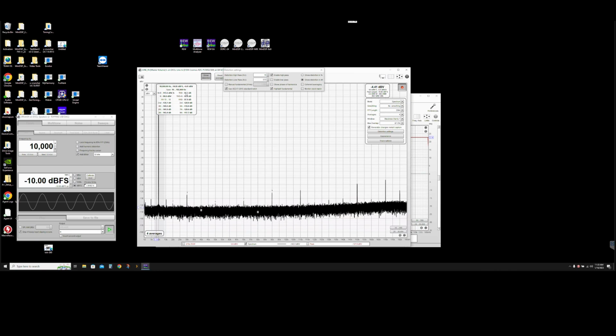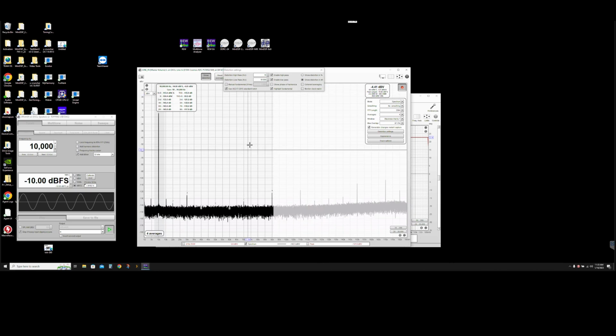You can see right now, it says our THD is negative 97 dB. But if you notice here, it's measuring harmonics all the way out as far as this goes. So it's measuring all of these harmonics. If we want a better idea, we can limit this to 91. And that's actually what our THD is, 115 and a half, not 97.